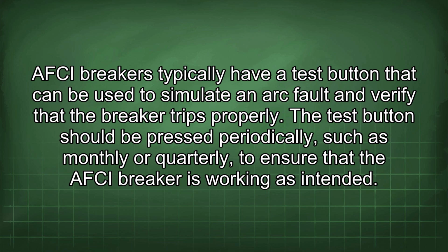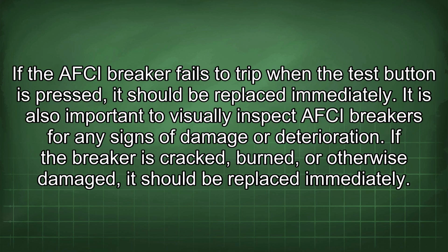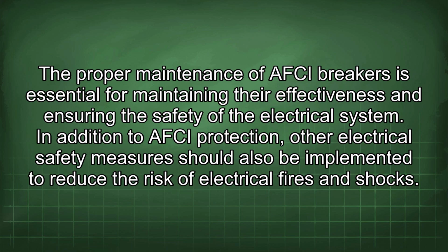AFCI breakers typically have a test button that can be used to simulate an arc fault and verify that the breaker trips properly. The test button should be pressed periodically, such as monthly or quarterly, to ensure that the AFCI breaker is working as intended. If the AFCI breaker fails to trip when the test button is pressed, it should be replaced immediately. It is also important to visually inspect AFCI breakers for any signs of damage or deterioration. If the breaker is cracked, burned, or otherwise damaged, it should be replaced immediately. The proper maintenance of AFCI breakers is essential for maintaining their effectiveness and ensuring the safety of the electrical system.